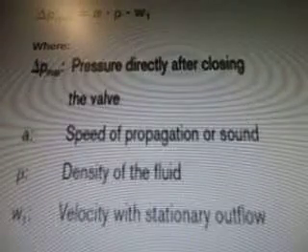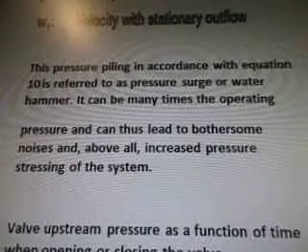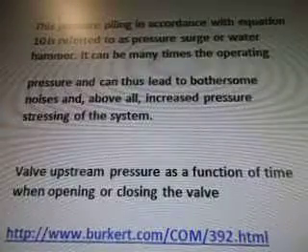So there's the equation there: pressure directly after closing valve, speed of propagation or sound, density of fluid, and velocity with stationary outflow. This pressure piling in accordance with equation 10 is referred to as pressure surge or water hammer. It can be many times the operating pressure and can thus lead to bothersome noises and, above all, increased pressure stressing of the system.